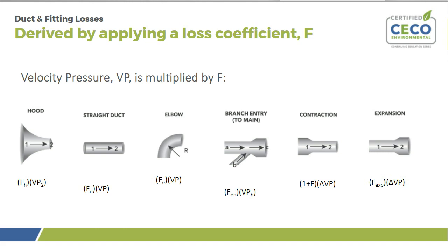For an elbow, we showed you an elbow with a 2D centerline radius. That loss is the result of turning the airstream within the duct, and the greater that R that you have, the less loss you're going to have. For a branch entry into the main, that loss is the energy required to blend the airstream from A and B where they join at C. And having that, it's also dependent on the angle.